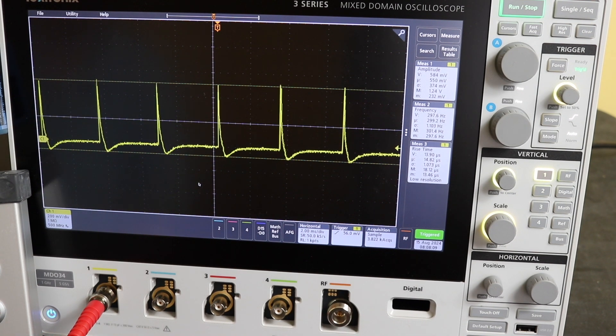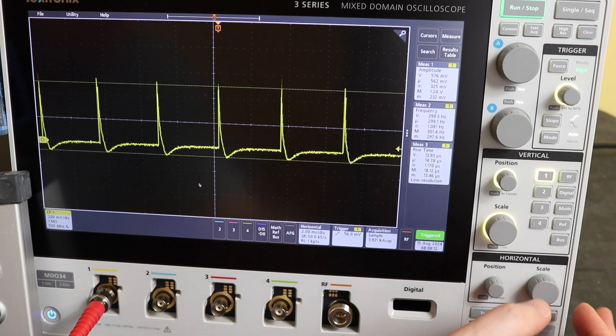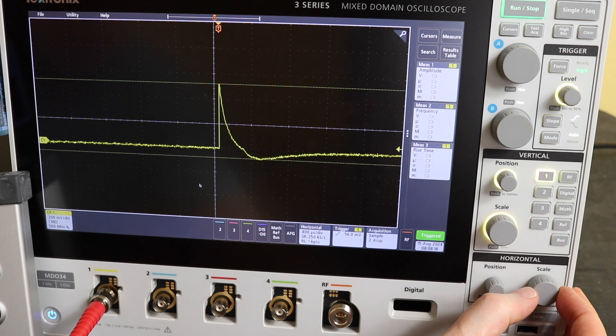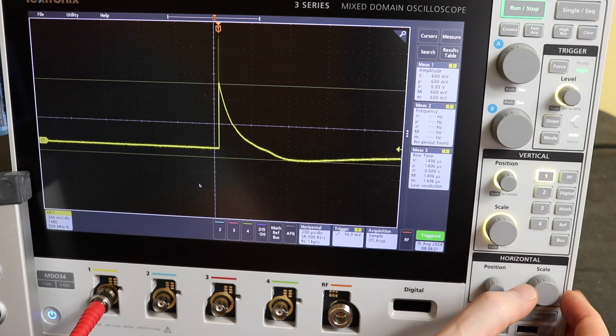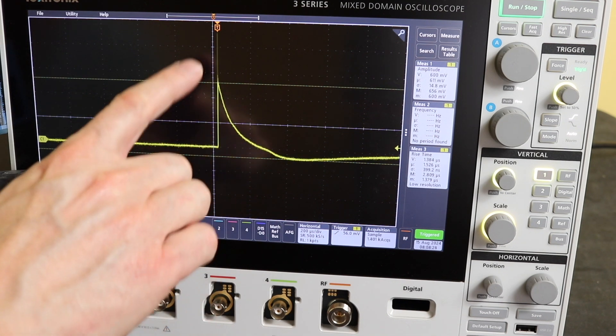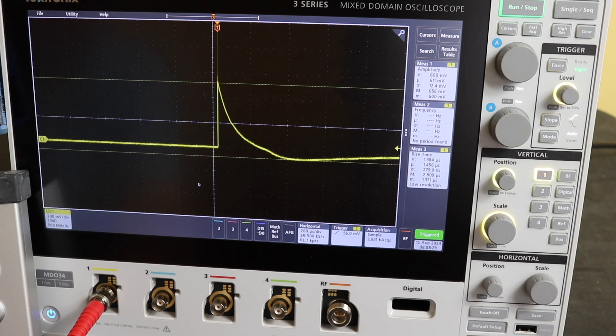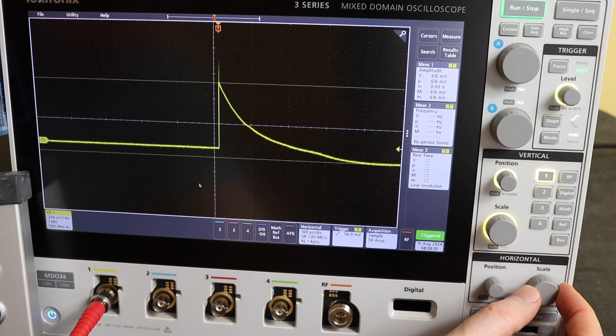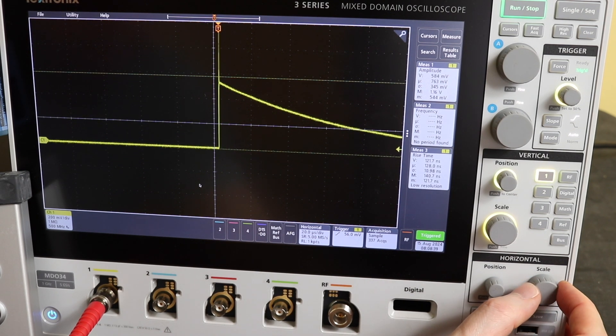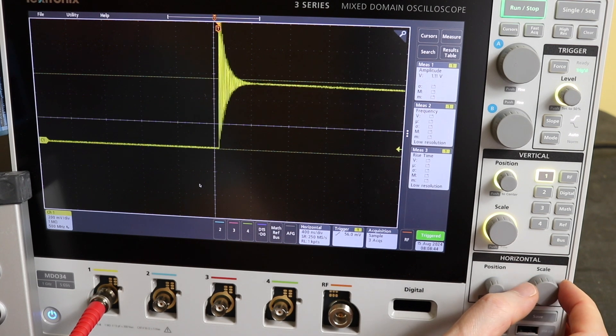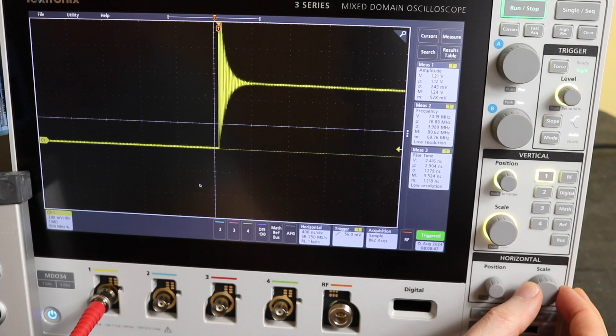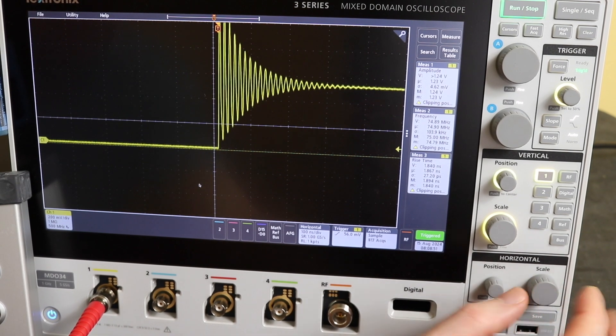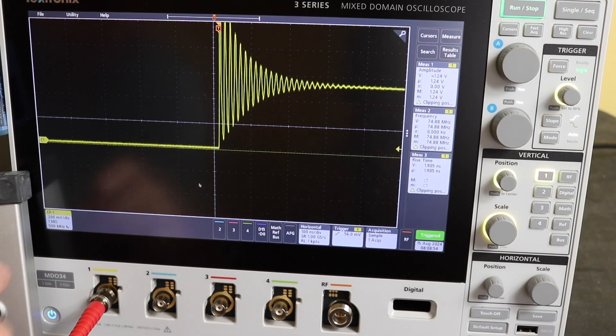We'll put it up there and we'll look at the actual rise time on an individual signal. Really expand it out. You can see this typifies a partial discharge pulse out on the system. It's very high rise time. We're now down to 1.5, 1.4 microseconds rise time on that signal there. We can go further if you like, we just probably won't get any better on it. The only danger is you can end up picking up, you can see there's a lot of ripple on here on the signal and that's therefore you see all the bounce there. It's just the nature of the signal really. Unfortunately, nothing we can do to get rid of that.